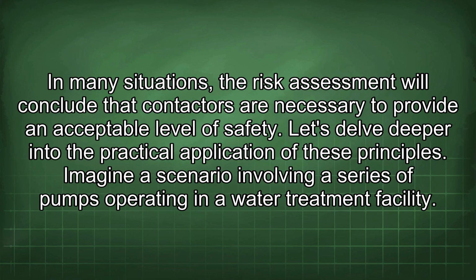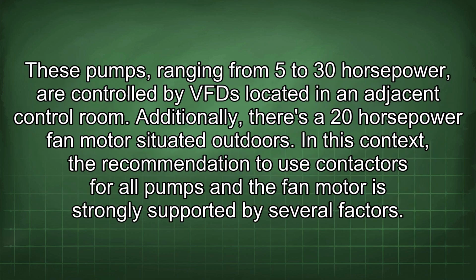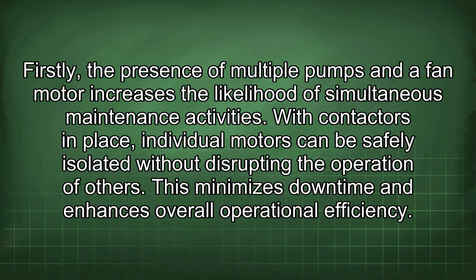Imagine a scenario involving a series of pumps operating in a water treatment facility. These pumps, ranging from 5 to 30 horsepower, are controlled by VFDs located in an adjacent control room. Additionally, there's a 20 horsepower fan motor situated outdoors. In this context, the recommendation to use contactors for all pumps and the fan motor is strongly supported by several factors. Firstly, the presence of multiple pumps and a fan motor increases the likelihood of simultaneous maintenance activities.